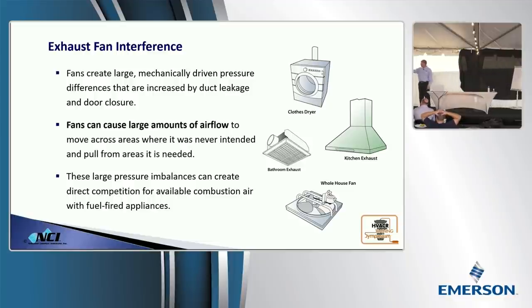If you kick on a clothes dryer, the old clothes dryers exhaust around 70 CFM. Some newer clothes dryers are double to triple that. So they say that they're more efficient. No, they're just moving more air. Look at the specs on them.